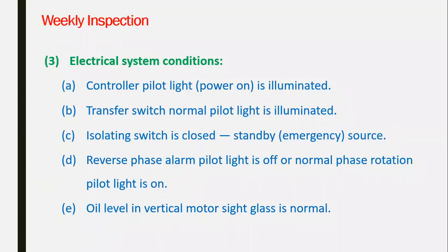The isolator switch, which is the main incoming for the electrical cables, is closed and connected for the standby emergency source. The reverse phase alarm pilot is off. The reverse phase is indicated on the cables and the feeder coming from the generator side. The standby side is off. It means that the phase sequence and operation will rotate the pump for pressurizing, not for suction, in the right direction. The oil level in a vertical motor sight glass is normal. If it has an oil indicator, check the oil level.